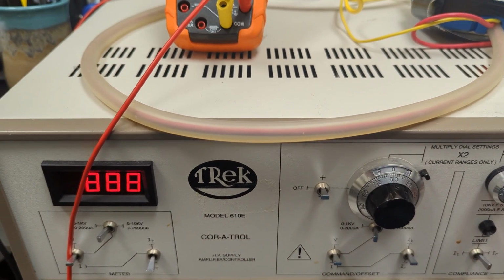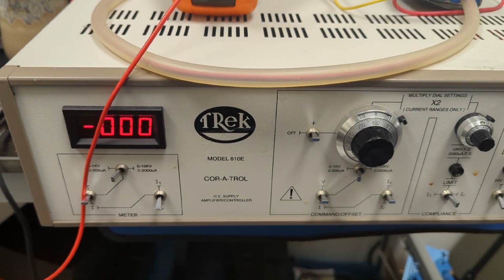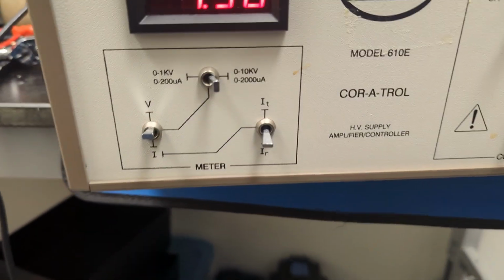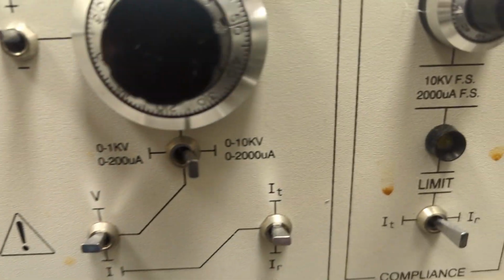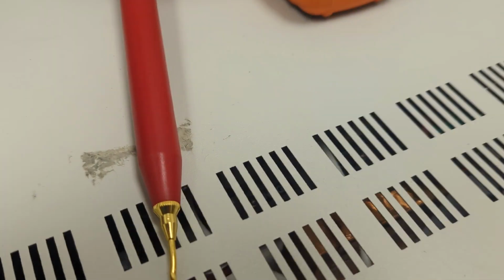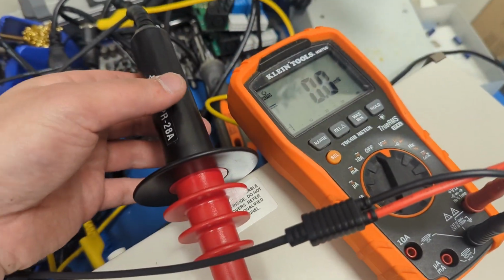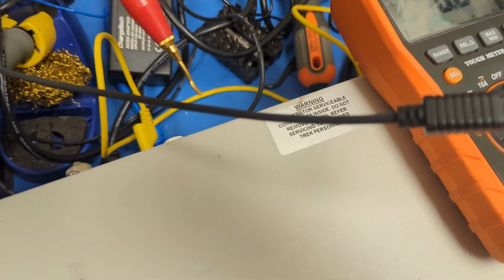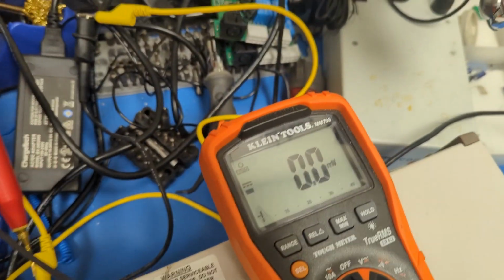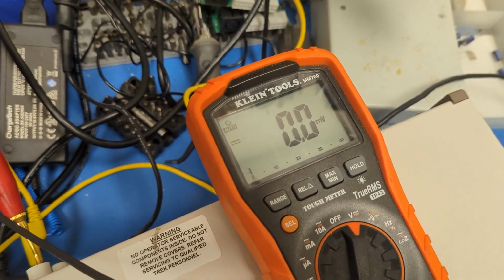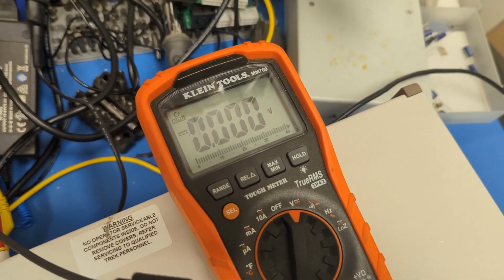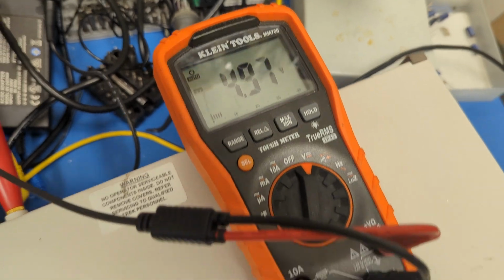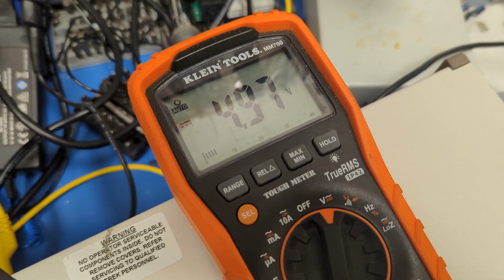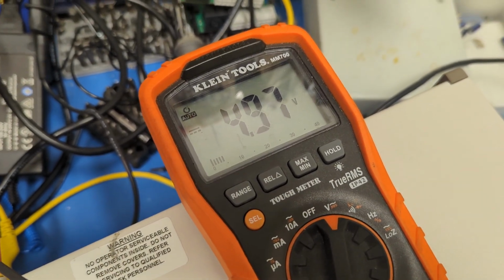All right. Let's check the higher range. All right, so we've got it set to the 0 to 10 kilovolt range. Got my high voltage differential probe. I got rid of that switch because it's a little sketchy, definitely for voltages over 1,000 volts. I can't reach, but that's very accurate. Awesome. Very cool.